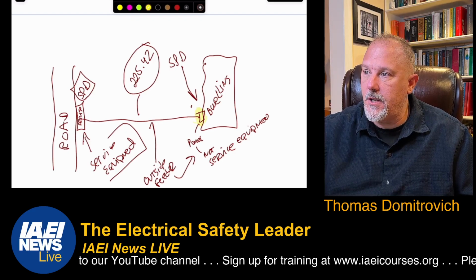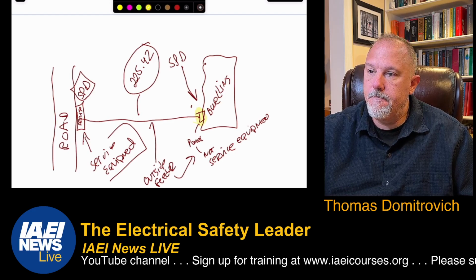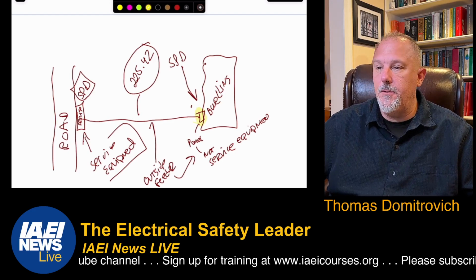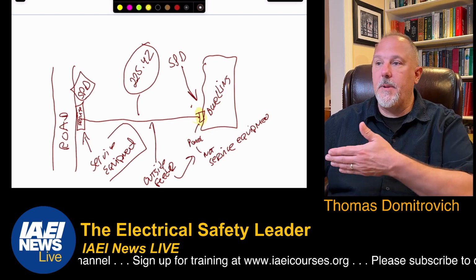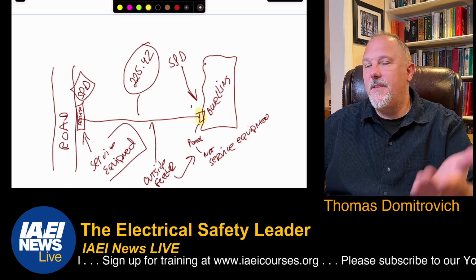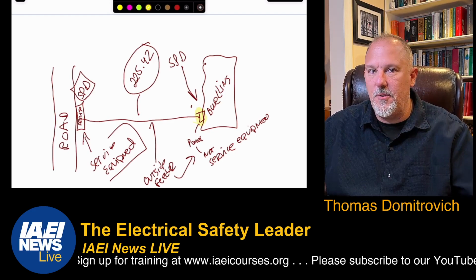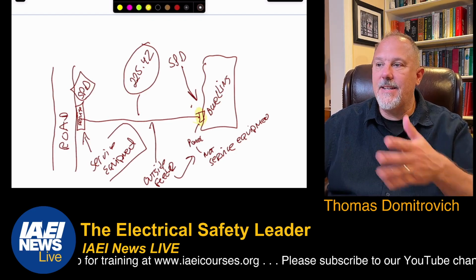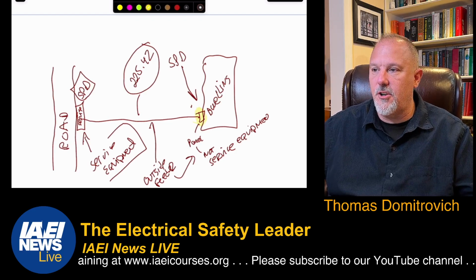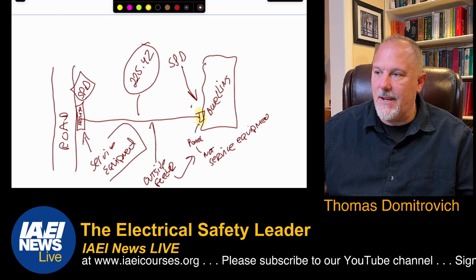That's where they want the surge. And they want it to be a type 1 or a type 2. And if you replace that equipment, then you need to make sure you put surge in there. And it has to be rated with a nominal discharge current of not less than 10,000 amps.